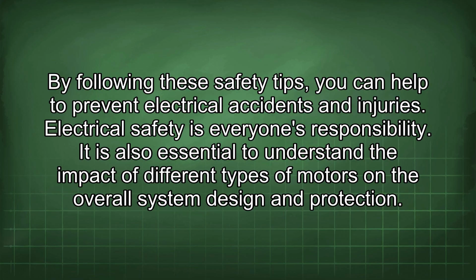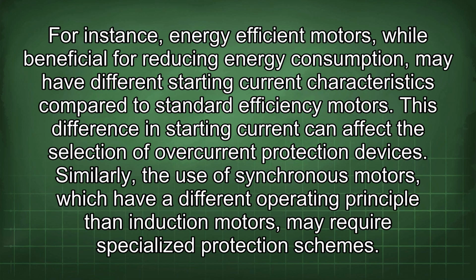It is also essential to understand the impact of different types of motors on the overall system design and protection. For instance, energy-efficient motors, while beneficial for reducing energy consumption, may have different starting current characteristics compared to standard efficiency motors. This difference in starting current can affect the selection of overcurrent protection devices. Similarly, the use of synchronous motors, which have a different operating principle than induction motors, may require specialized protection schemes.